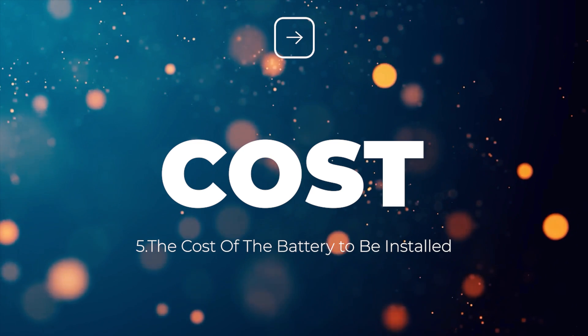Finally, you need to consider the cost. A convenient way to compare battery cost is on a cost-per-kilowatt-hour basis, since different batteries come in different sizes. For example, Franklin's battery is 13.6 kilowatt hours per unit versus Enphase's battery at only five kilowatt hours per unit, meaning you may need to compare two or three Enphase batteries against one Franklin battery. The easiest approach is to take the total cost of the proposed installation, divide by the total kilowatt hour storage, and that gives you a cost-per-kilowatt-hour figure for an apples-to-apples comparison.